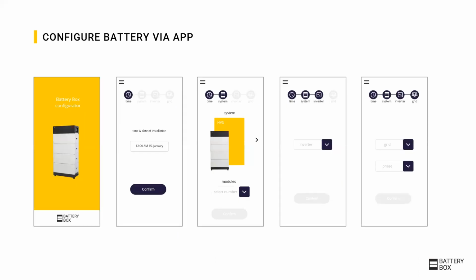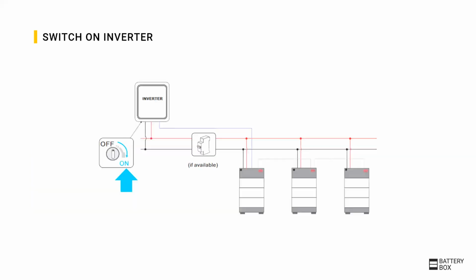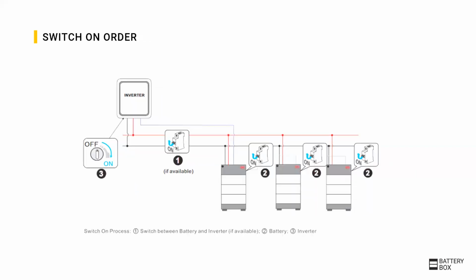The configuration asks for only very few pieces of information: the current time on the inverter, the battery configuration, the type of use, and phases. After the update and the configuration are done, you can switch on the inverter. Please install and configure the inverter based on the manual and requirements of the inverter manufacturer. In general, the startup procedure for the system should be first the switch between battery and the inverter, if there is any, then the battery or batteries, and then the inverter.